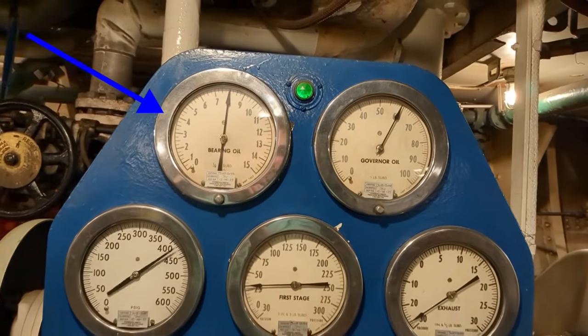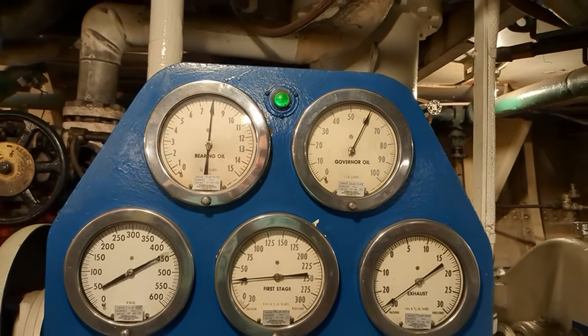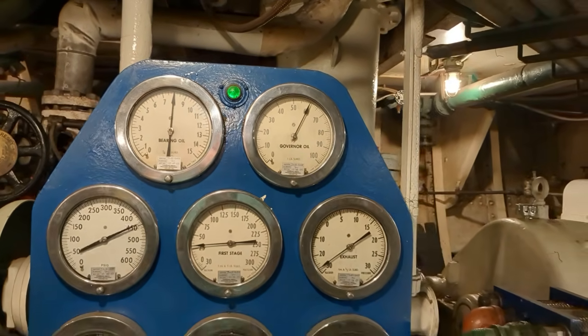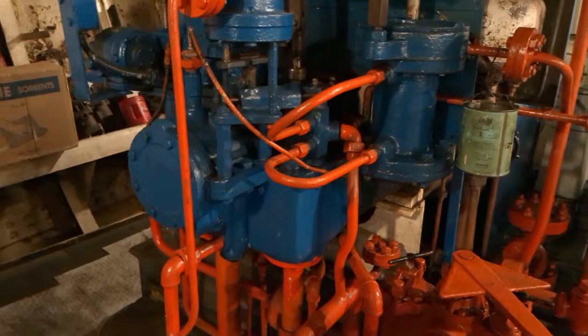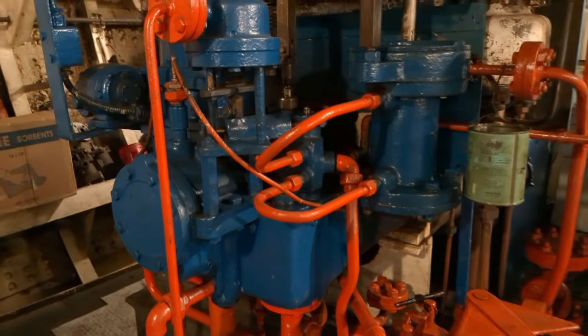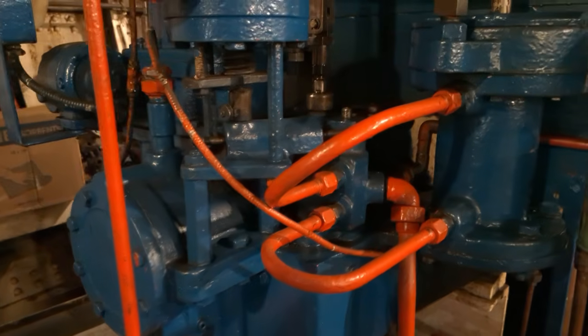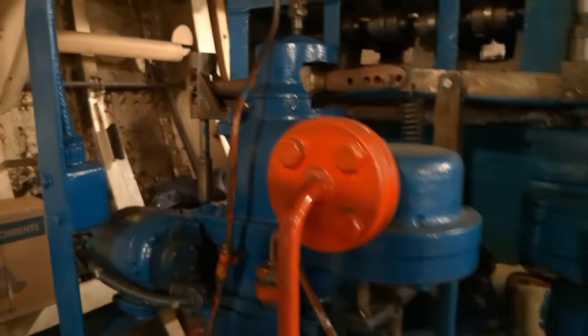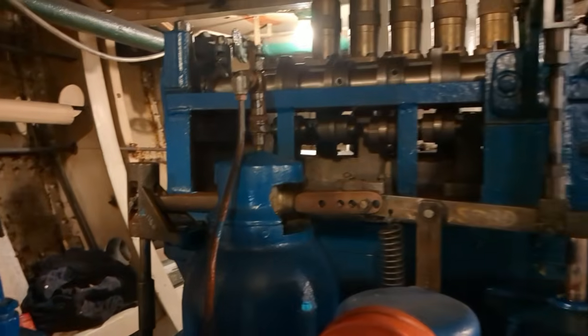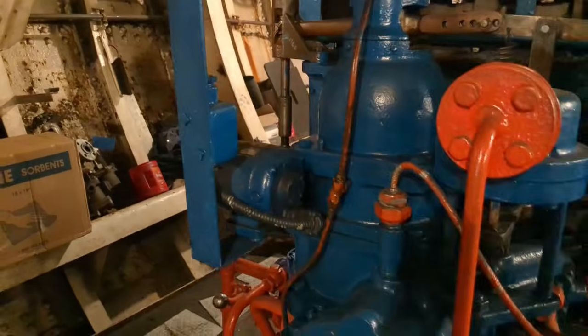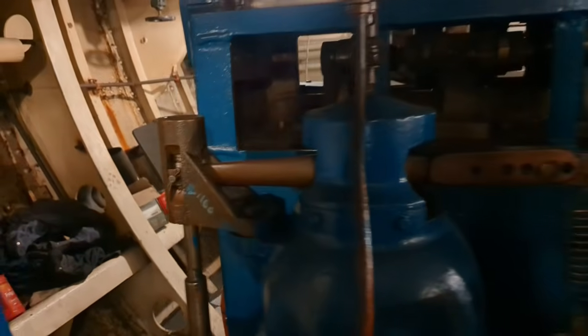Oil pressure is needed for lubrication and regulating speed, and these gauges indicate the pressure. This is the governor. It uses centrifugal force to keep the generator's RPM steady to produce 60 cycles AC. Inside this housing are the fly balls and pilot valve.